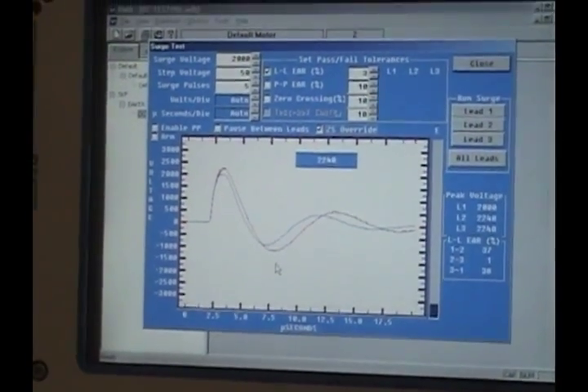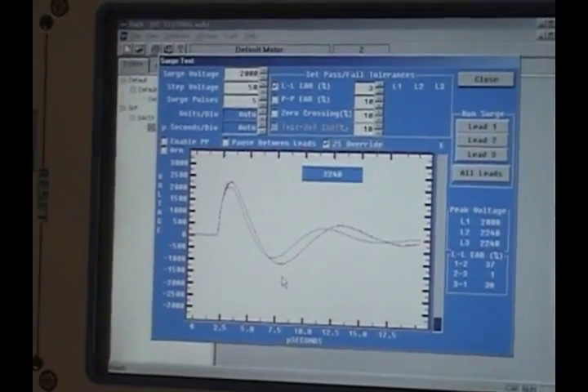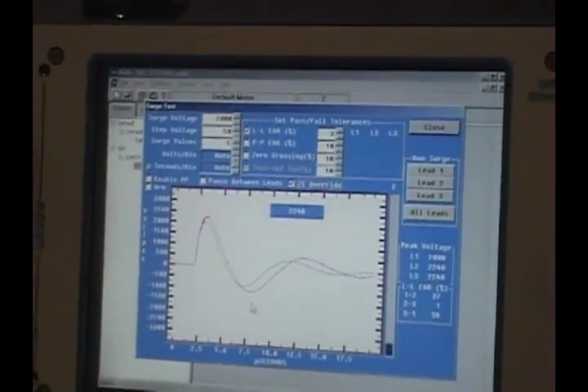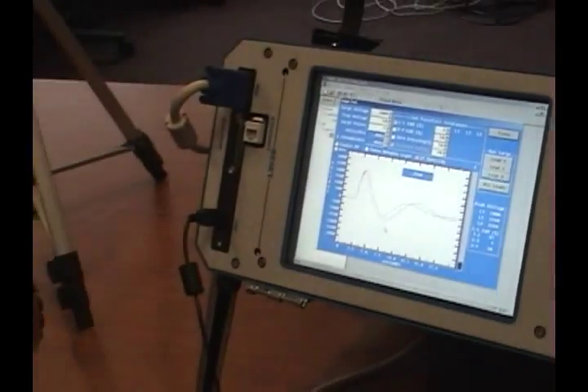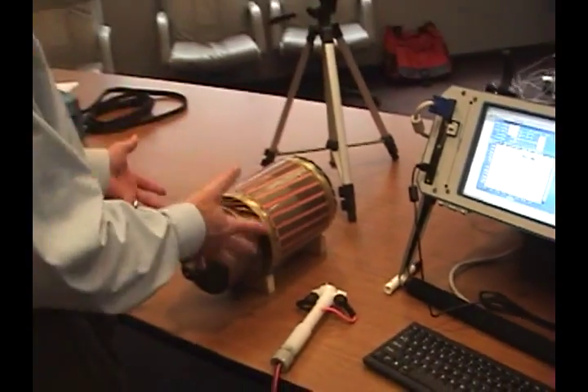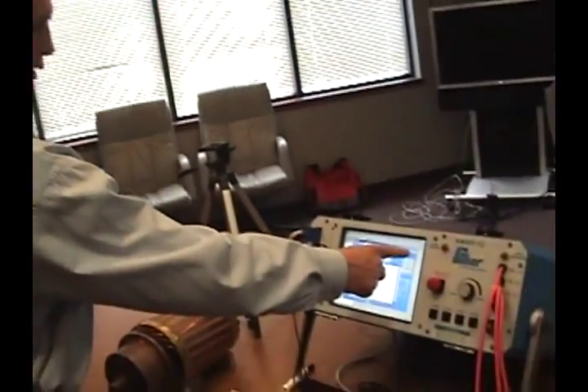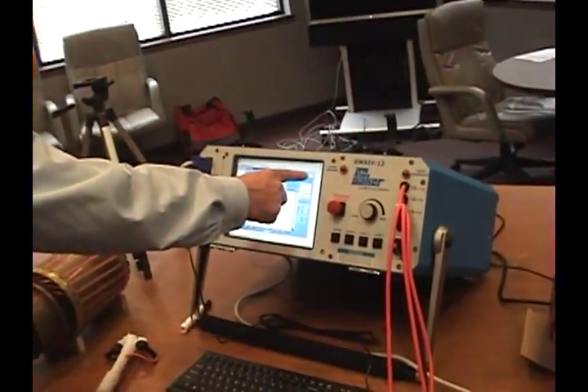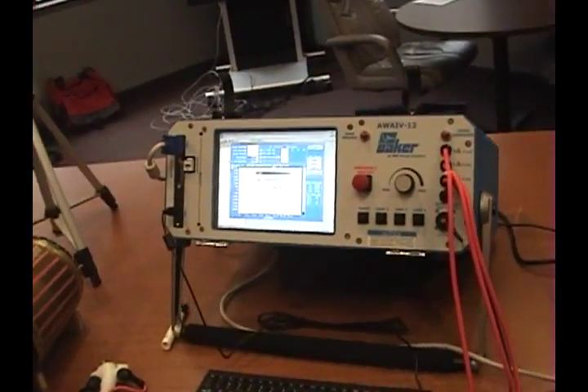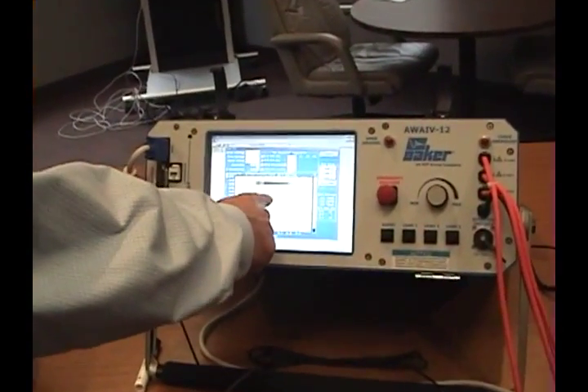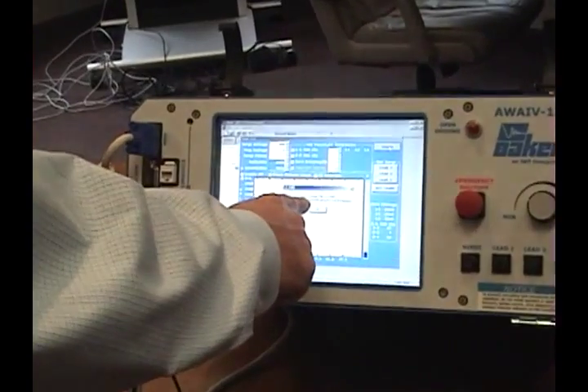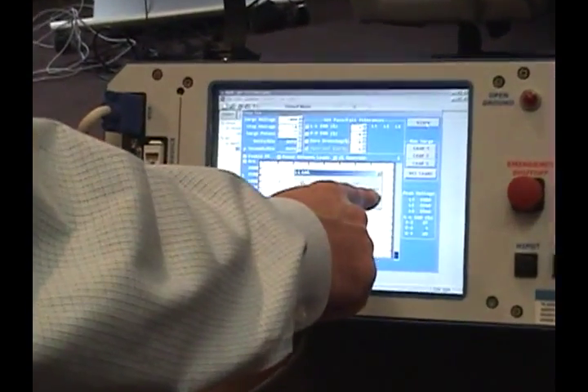Now, if we continued all the way around and everything else was good, or when we're finished testing the DC armature, we're going to close the screen. Close the screen. It says surge lead L2L EAR percentage is out of tolerance. We say okay.